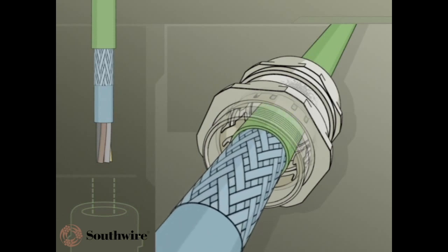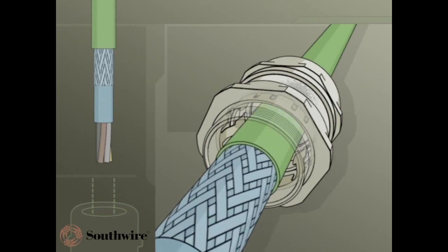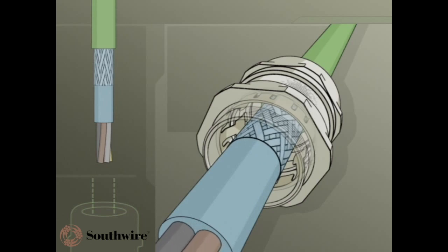Once the cable is cut back, insert the cable into the gland, positioning it so the jacket edge is pushed past the polyamide clamping insert and the shield is under the contact spring pads.